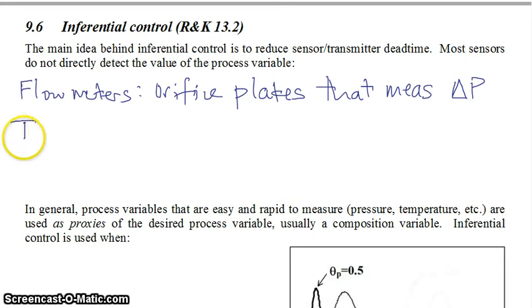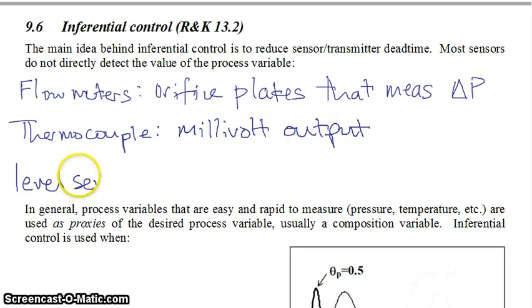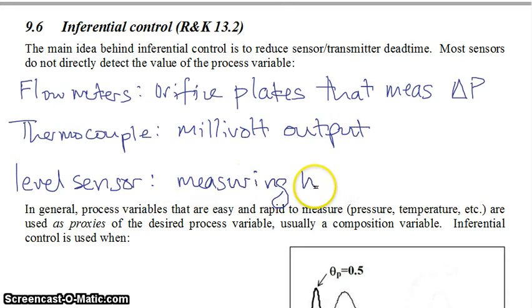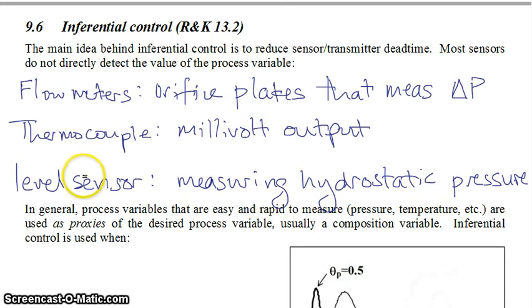Or you might have a thermocouple. A thermocouple is not actually really measuring the temperature — it's measuring some millivolt output. Or a level sensor is often measuring hydrostatic pressure. And there needs to be a good model which converts what the sensor is actually measuring into the thing that you want it to measure. Another example is a thermometer, which measures the height of a mercury column or an ethanol column, and that has to be really well correlated to temperature so you can read the temperature off the thermometer.